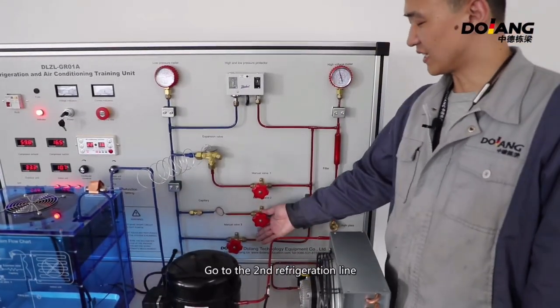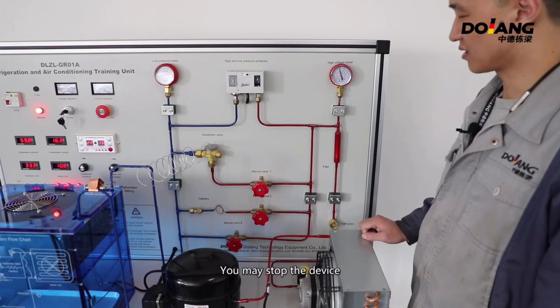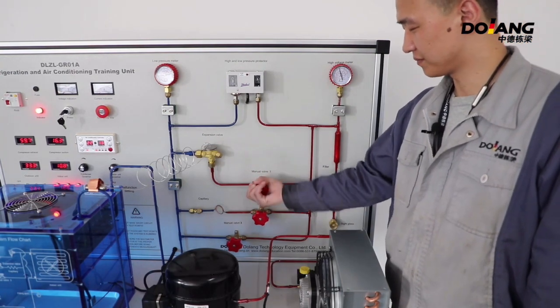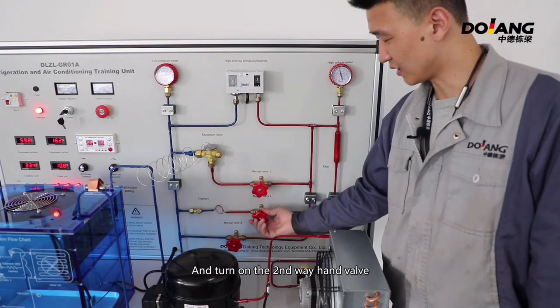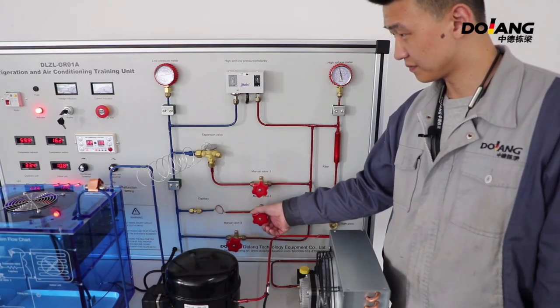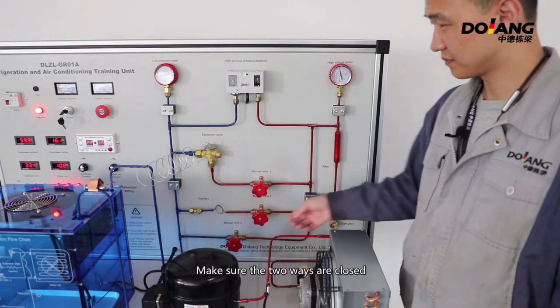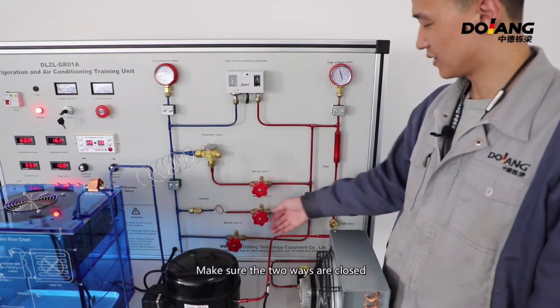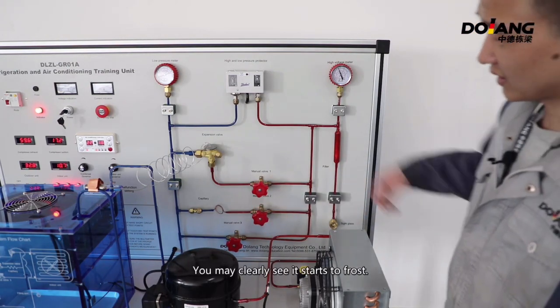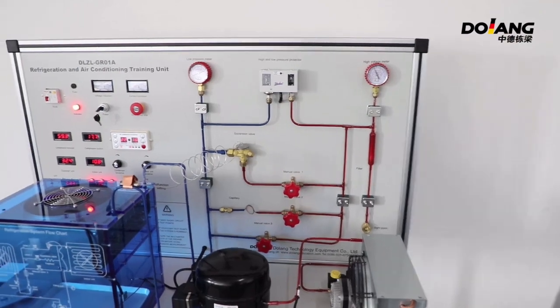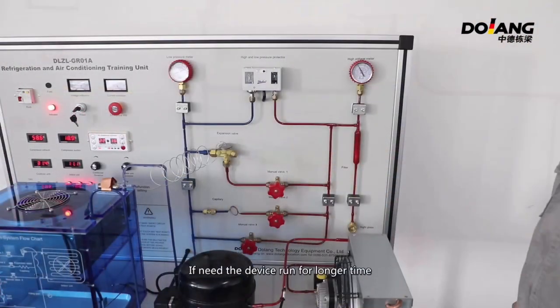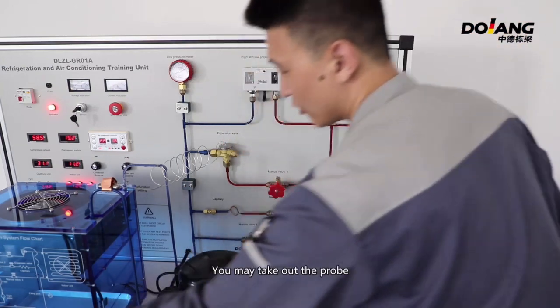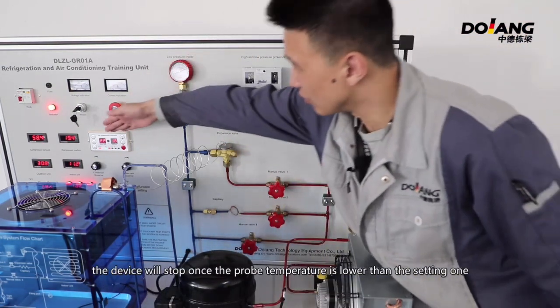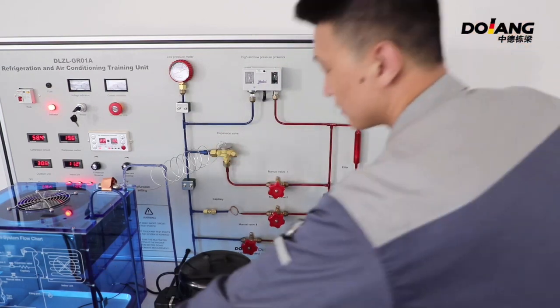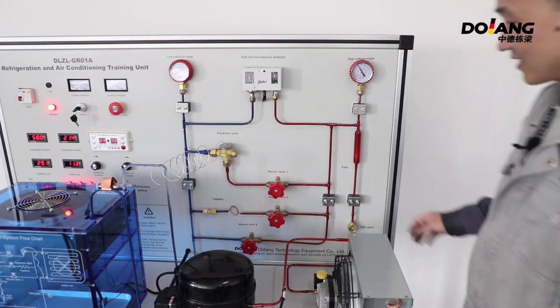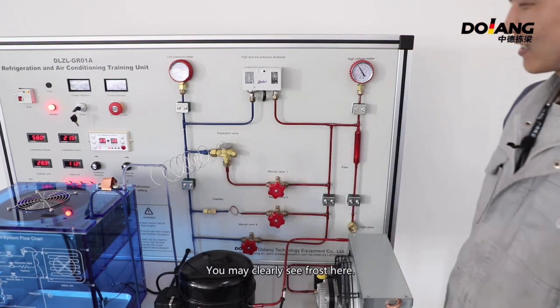Go to the second refrigeration line. You may stop the device. Also may turn off the first way hand valve, and turn on the second way hand valve. Make sure the other 2 ways are closed. You may clearly see it starts to freeze. If you need the device to run for a longer time, you may take out the probe. If you put it inside the evaporator, the device will stop at once when the probe temperature is lower than the setting one. You may clearly see frost here.